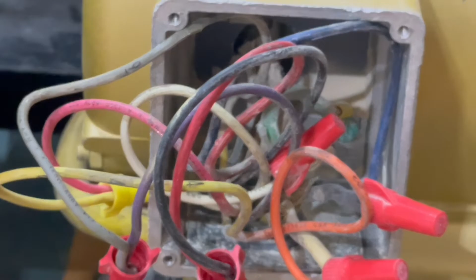Now we're done. We have wired a hot wire to wire number 1, a hot wire to wire number 2, and a hot line to wire number 3. Then we've connected the 6 and the 9, the 5 and the 8, and the 4 and the 7. We have no unaccounted for wires in our box, so this machine has now been successfully rewired to high voltage.